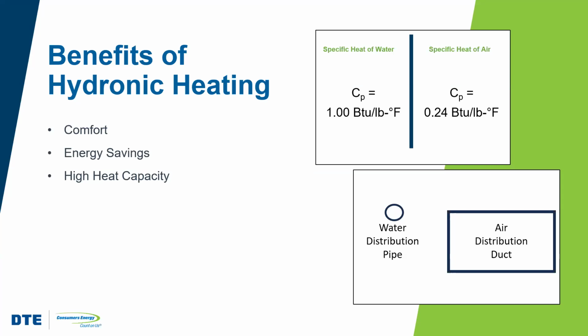And additionally, that tubing doesn't take up nearly as much space as the ductwork, right? So for the same temperature differential, for example, between the working fluid, either the air or the water, and the ambient air, right? The air system would have a greater heat loss, right? Because it's got greater surface area, right? And it's going to require more insulation. That's going to be adding additional cost to the project.